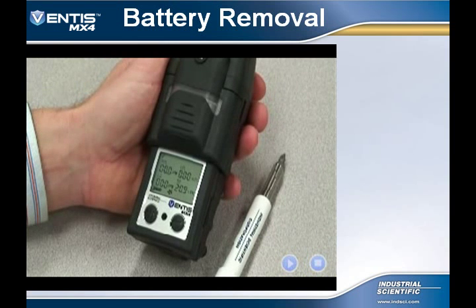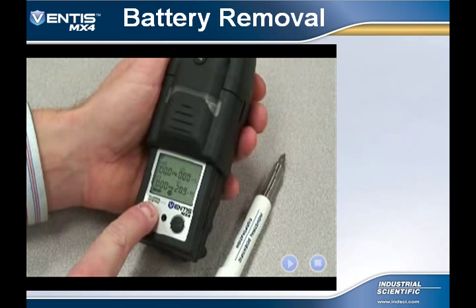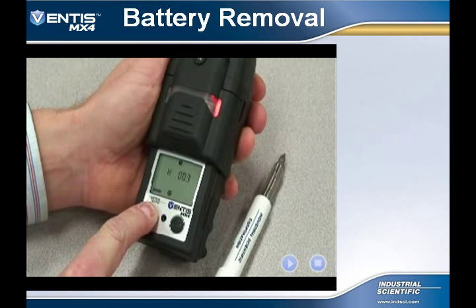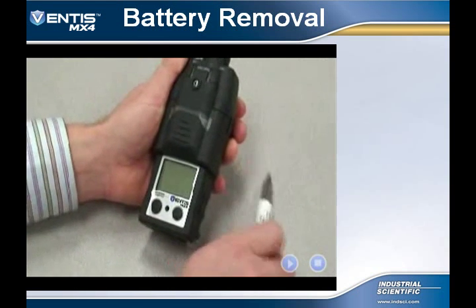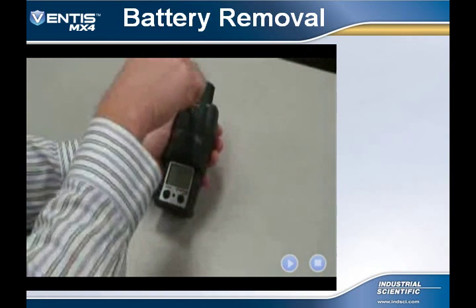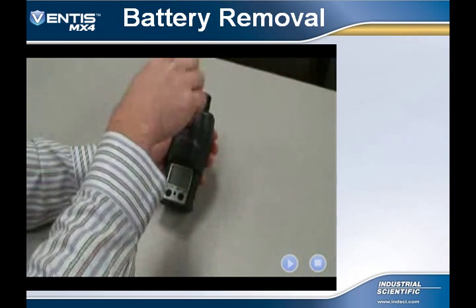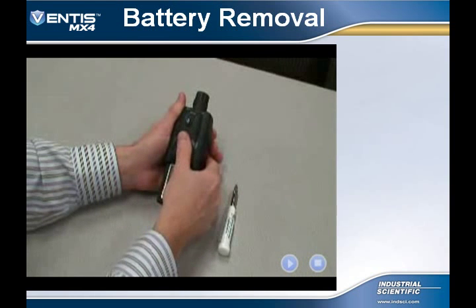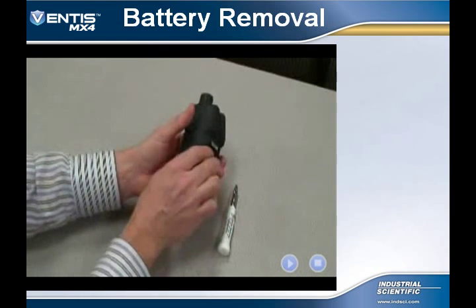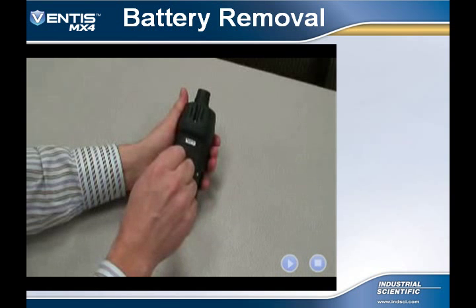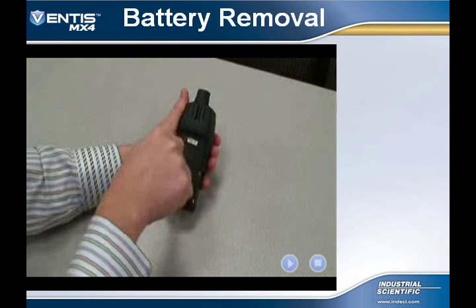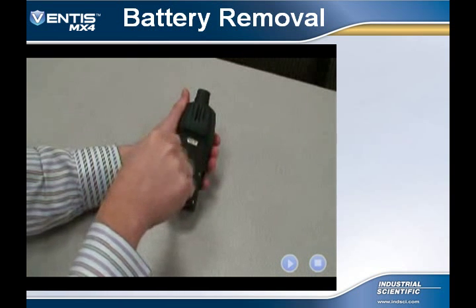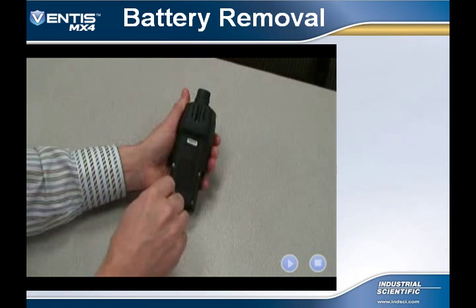Here you will see a video on how to remove a battery pack from the instrument. First, if the instrument is on, hold down the on-off mode button for 5 beeps to shut the instrument off. First, loosen the single captive screw on front of the instrument. Next, rotate the instrument on its back and loosen the 4 captive screws located on the back of the pump housing.